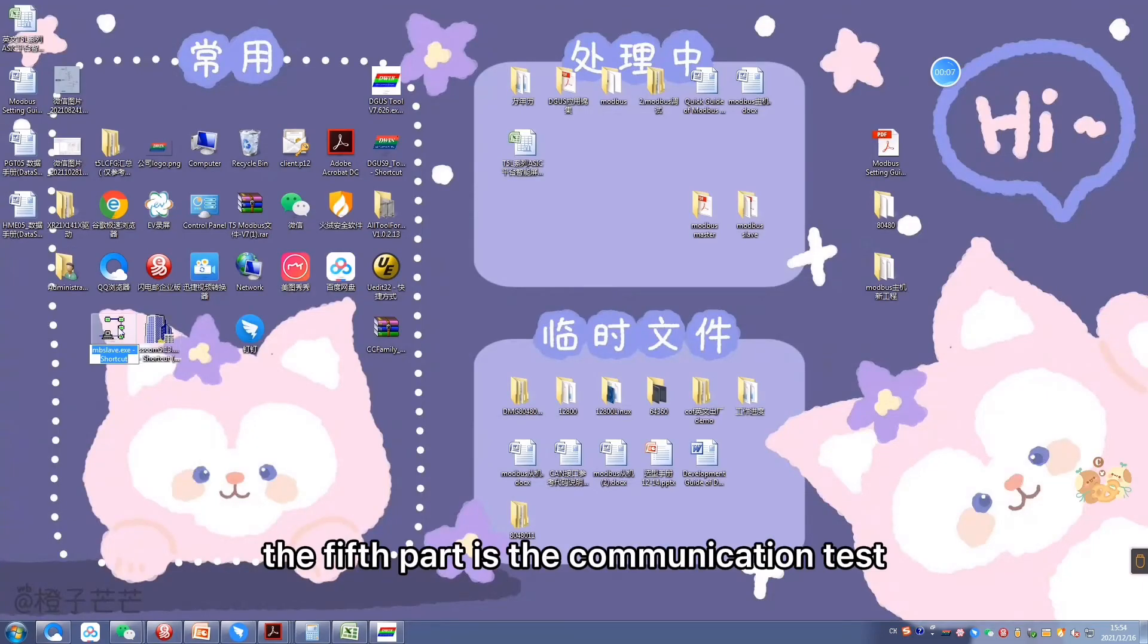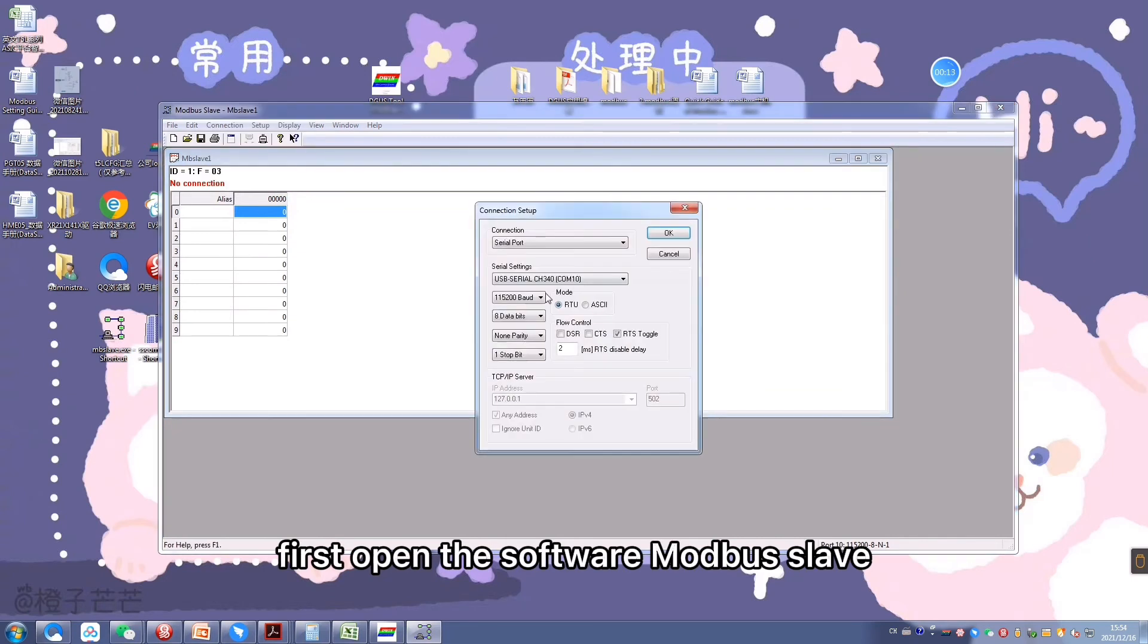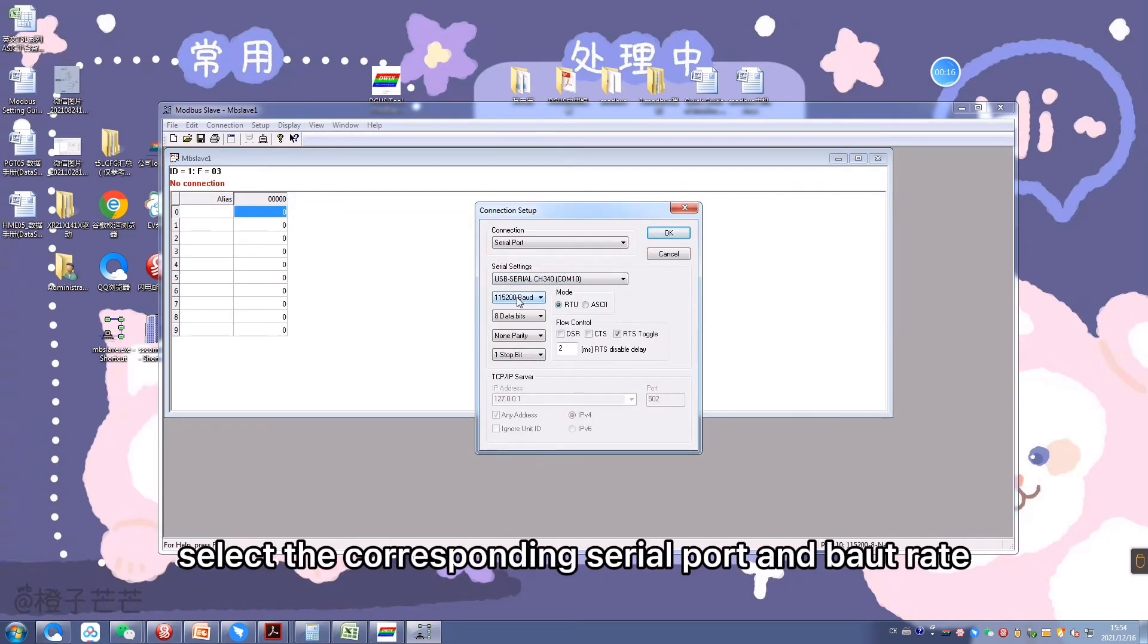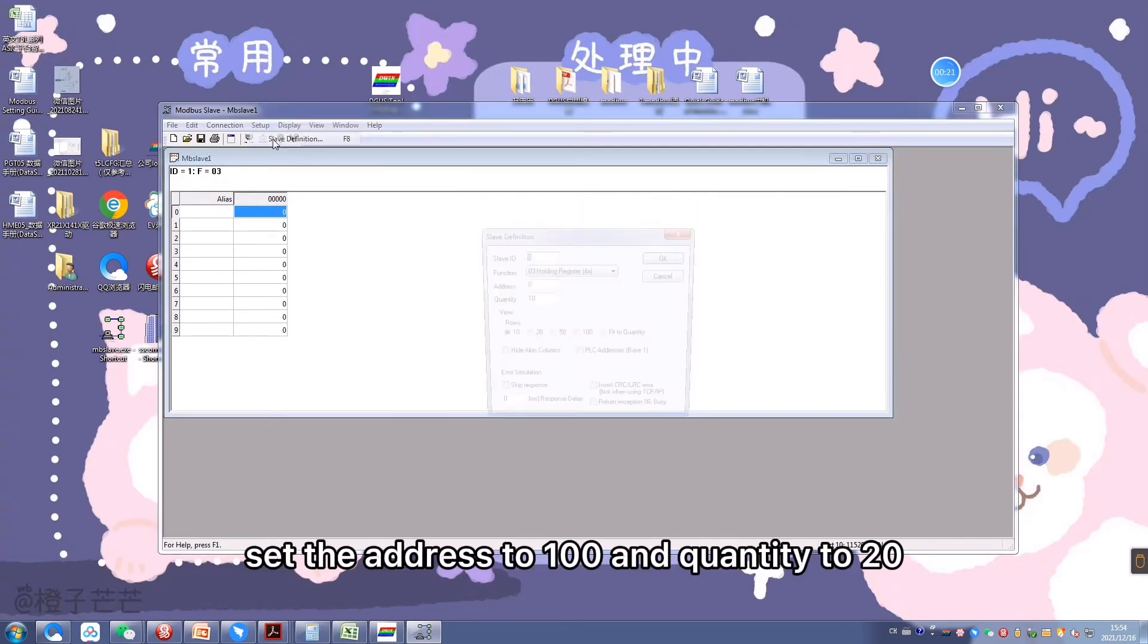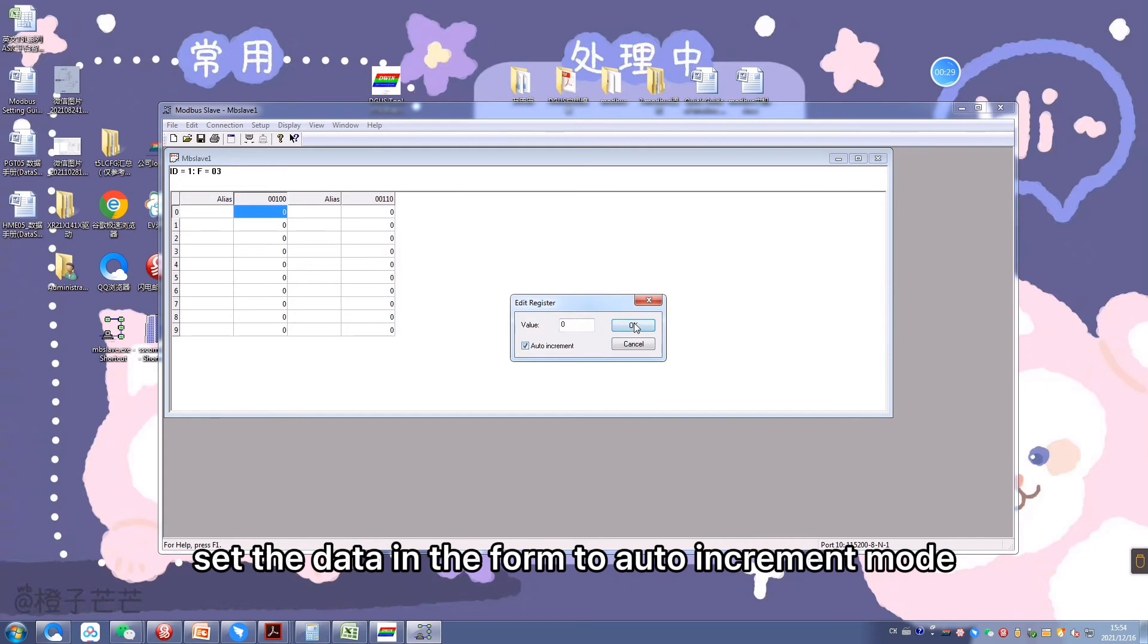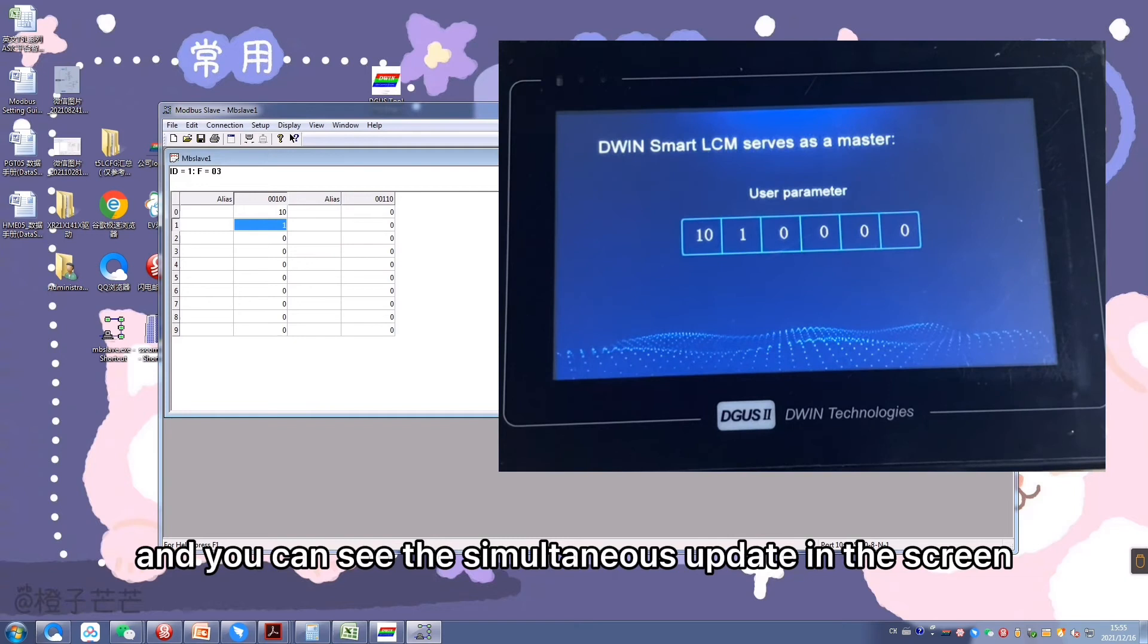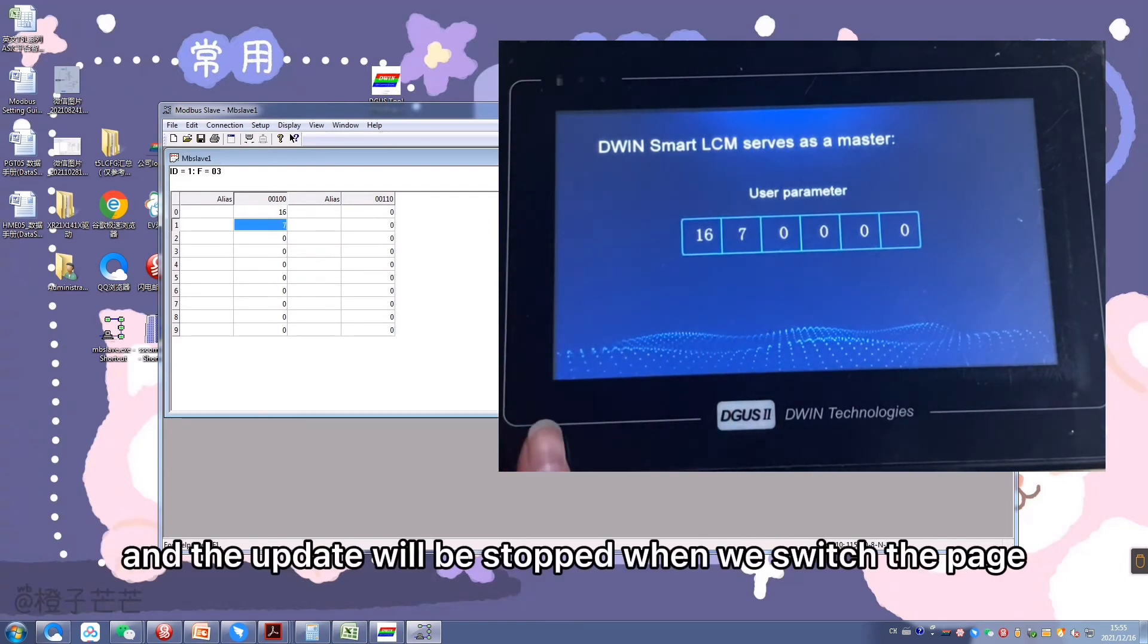The fifth part is the communication test. First, open the software Modbus Slave. Select the corresponding serial port and baud rate. Set the address to 100 and the quantity to 20. Set data in the form to auto-increment mode. And you can see the simultaneous update in the screen. And the update will be stopped when we switch the page.